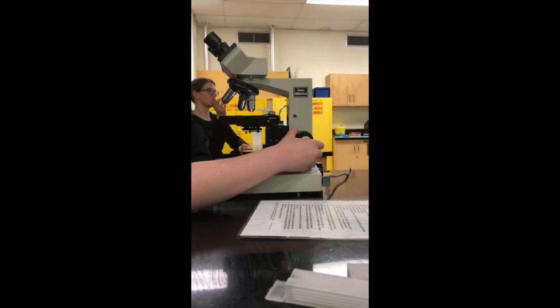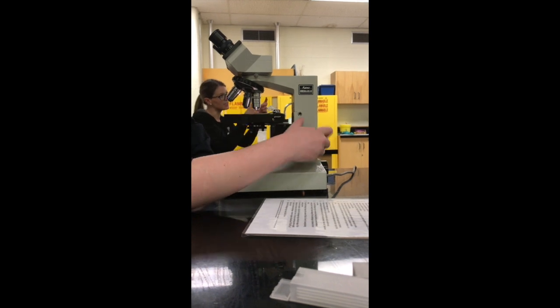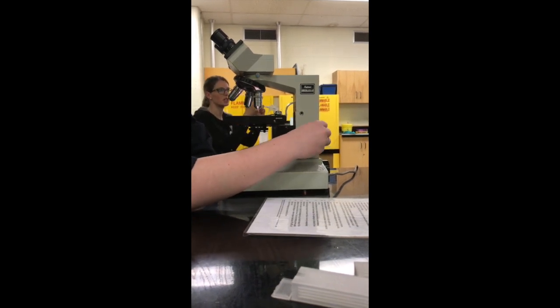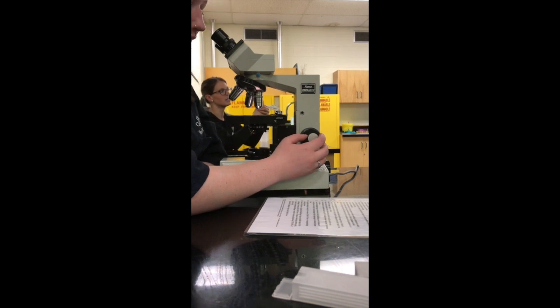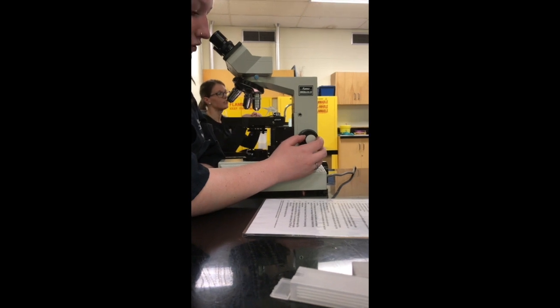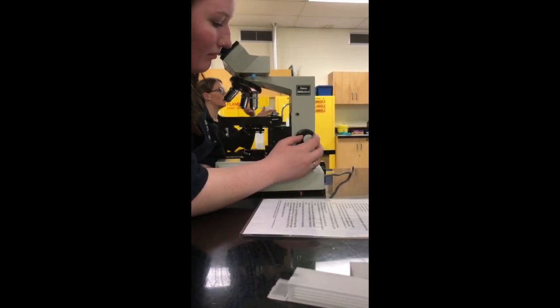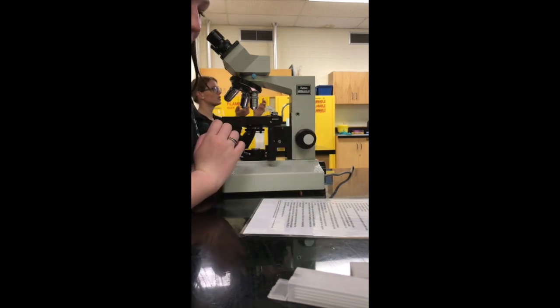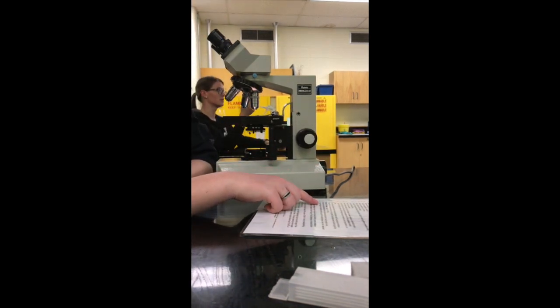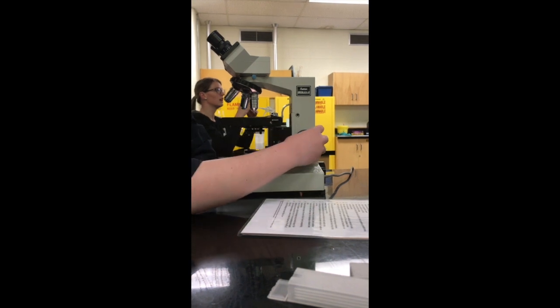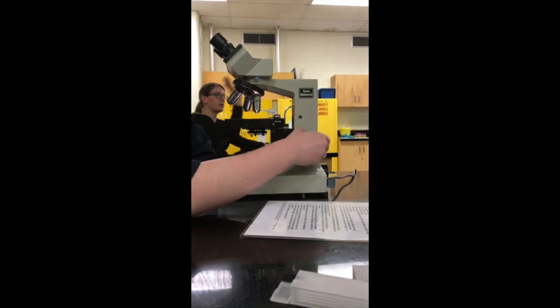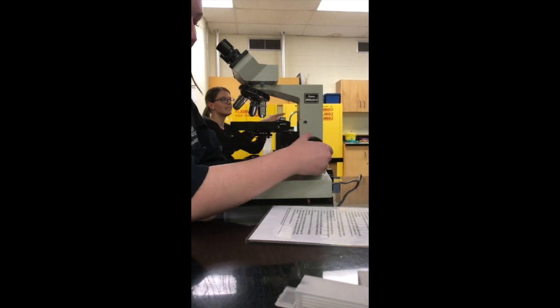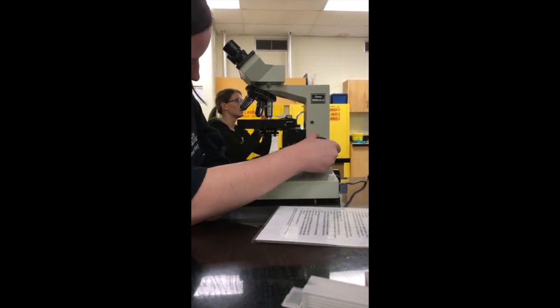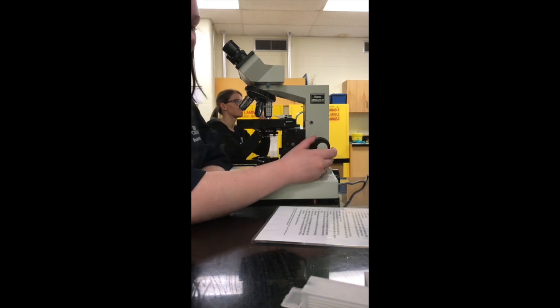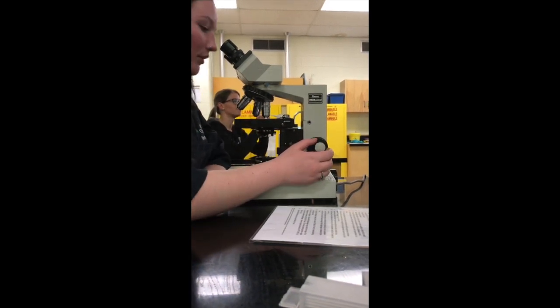Now I'm going to turn the coarse adjustment knob counterclockwise until the stage stops at the bottom. And I'm going to turn the fine adjustment knob so that the index ring is at the center of its range. And I'm going to rotate the coarse adjustment knob clockwise, bringing the stage up. Someone asks what to do in practice if having trouble with the microscope: if for some reason that wasn't working, I would go back and set my microscope up again and start again and see if maybe something was off. And I'm going to look through the eyepieces and use the fine adjustment knob until the specimen is in focus.